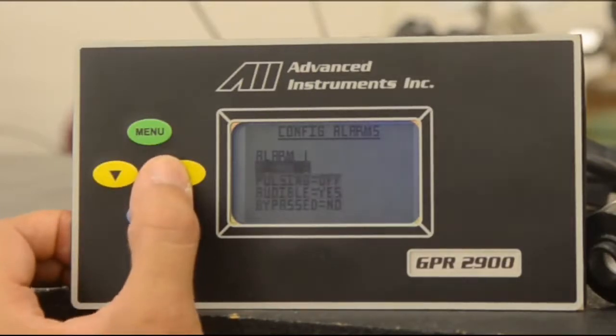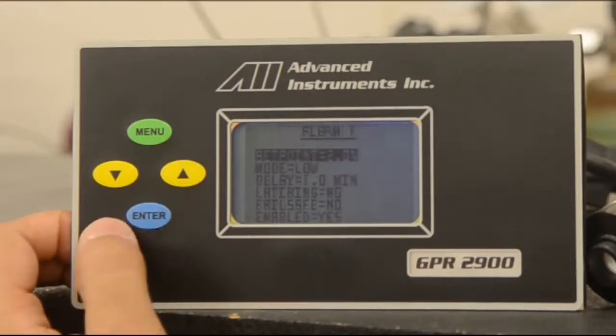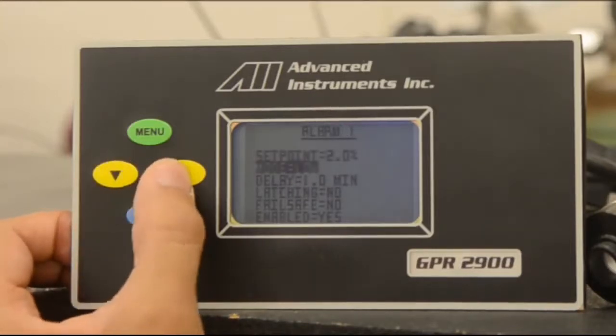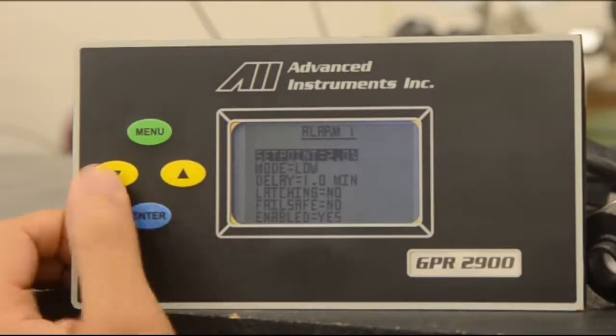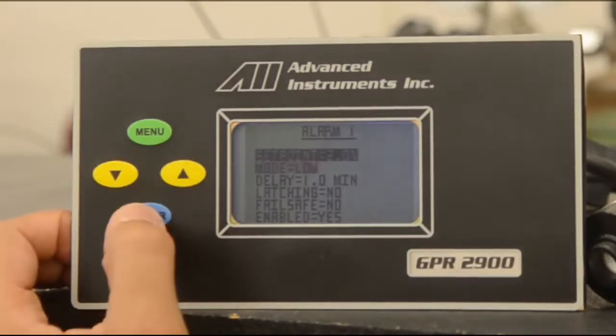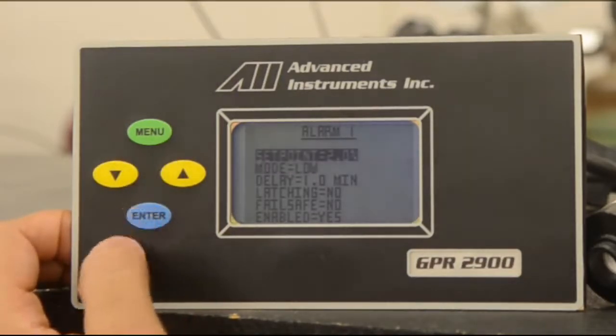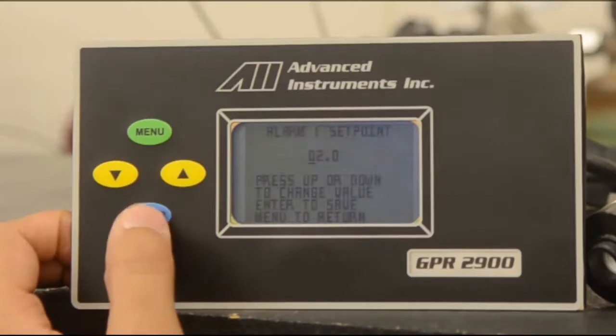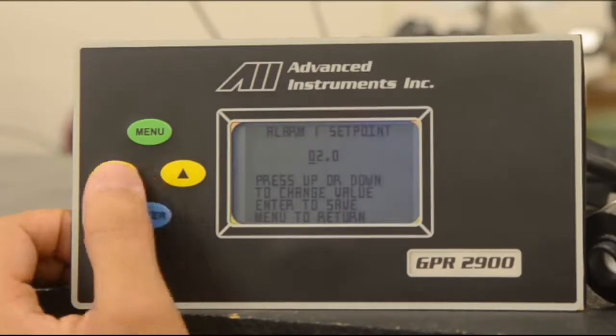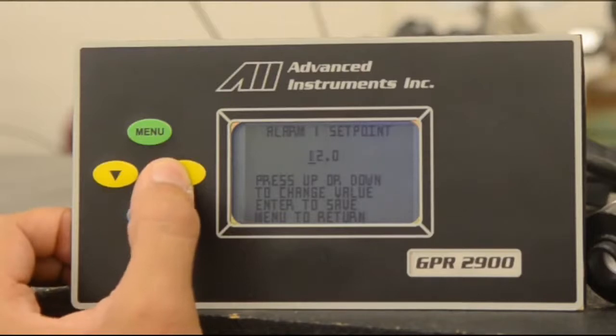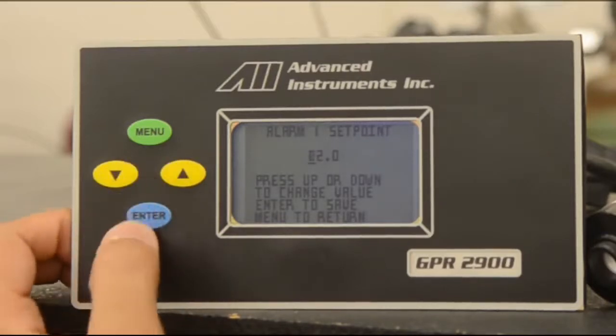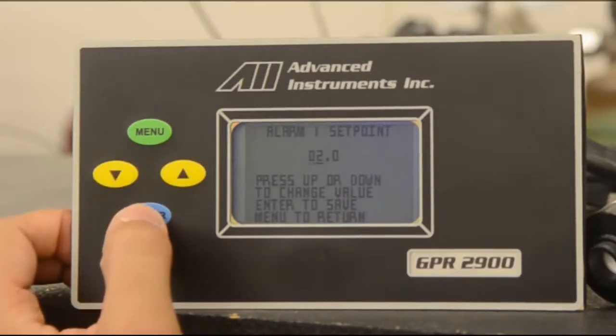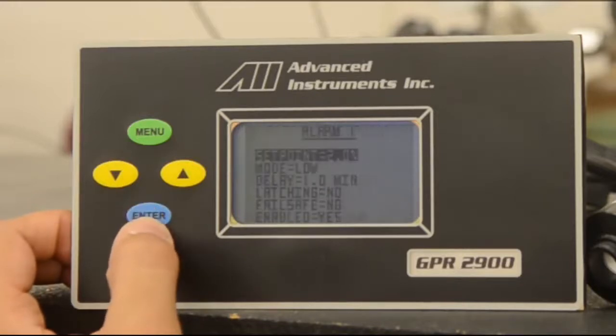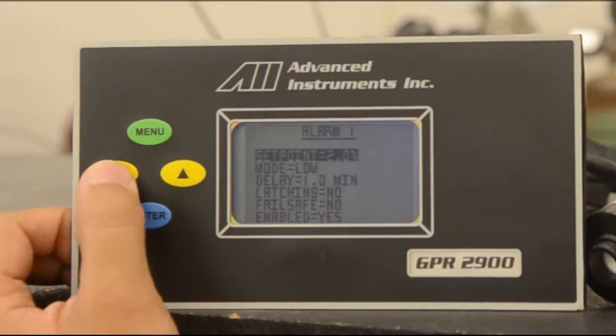Now, we scroll back up to alarm 1 and press enter. We have a set point at 2% at mode low. These can both be changed and are user configurable. You press enter and you are prompted to the screen to change your values. Again, you hit up or down to change the level and enter to change your decimal point. Continue to hit enter to exit that screen and set your value.